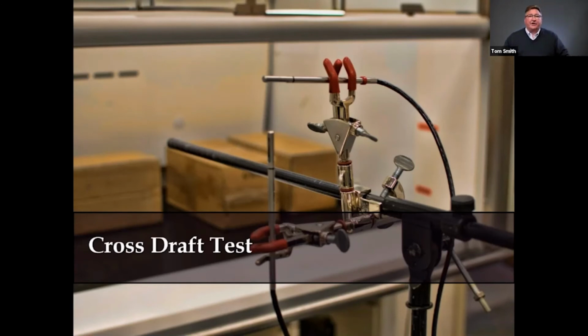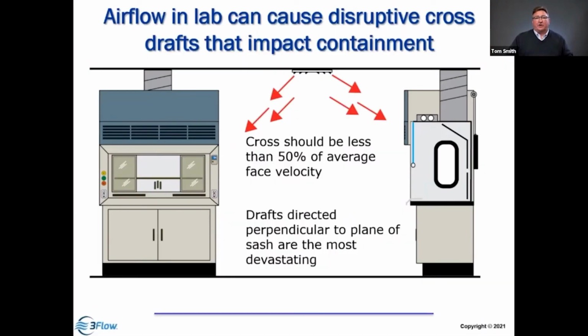All right, moving on to the cross-draft tests. You may not think cross-drafts in the lab can impact the performance of a hood, but they're really quite important, because if you can feel the air being supplied into the space blowing on you, it's much greater than 100 feet per minute. 100 feet per minute face velocity is about 1.2 miles per hour. If you were a sailor out on a boat on a lake at 1.2 miles an hour, I'm telling you, you're not going to go anywhere, right? It's a very low velocity. It sounds like a lot in terms of a fume hood, but it's actually very, very low speed.